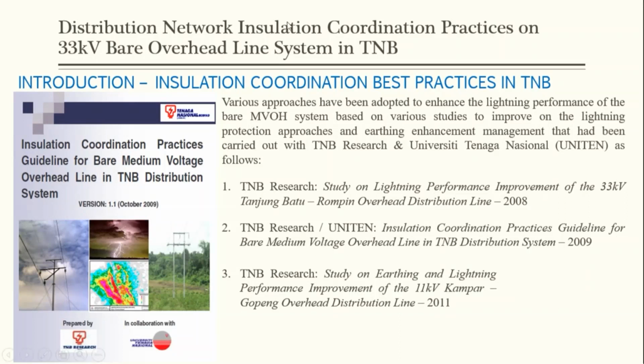So we have this guideline. This is the cover of the guideline that we published in October 2009 for the use of our engineers, planners, and also technicians. And thirdly, we have the TNB Research study on earthing and lightning performance improvement of the 11 kV Kampar-Gopeng overhead distribution line in 2011. So we have done a lot of study to improve on the insulation coordination in TNB. Why? Because the GFD level in Malaysia is so high.